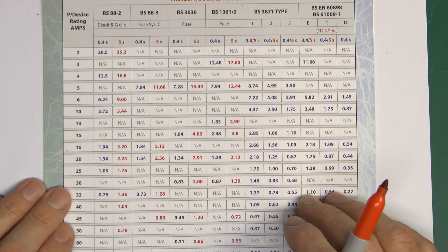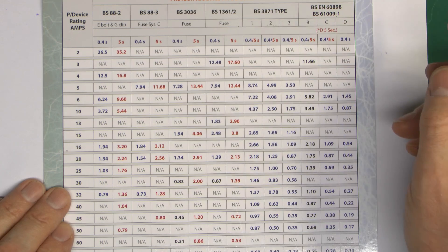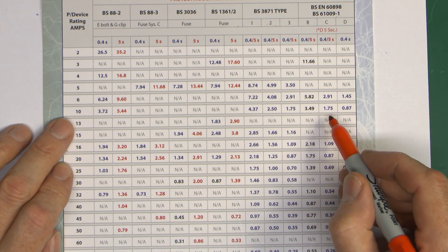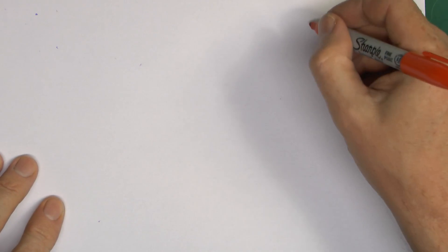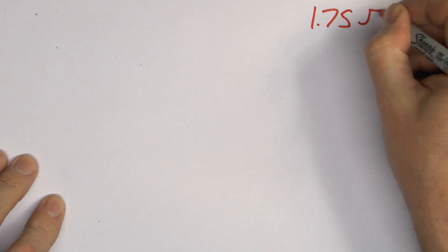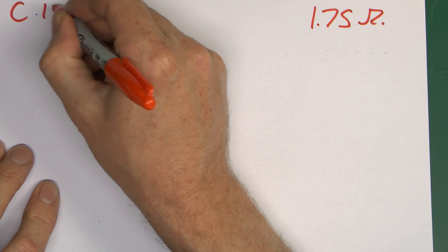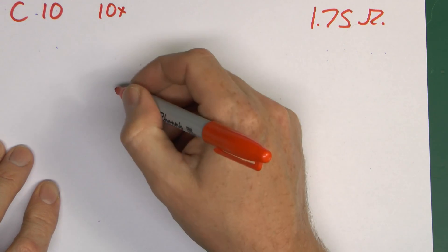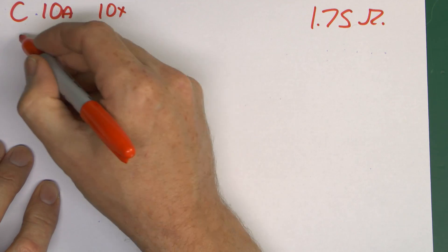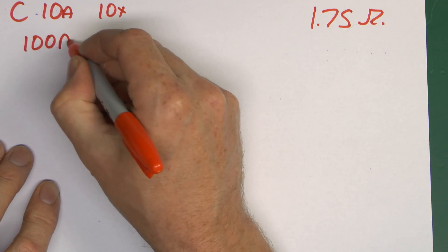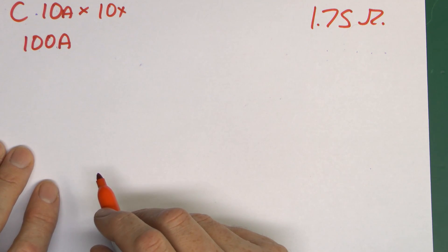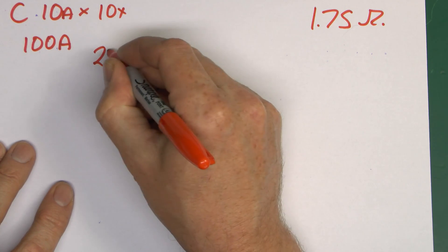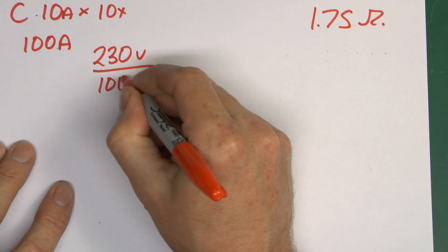Now I'll just do another one of these calculations quickly here, just to demonstrate that. This time, let's say it was a Type C, and this time it was a 10A circuit breaker. So Type C, 10A, so it should be a value of 1.75. So 1.75 is what it's supposed to be. So a Type C, and it was a 10A. Now Type C is tripped between 5 and 10 times, so we're going to assume it's going to be the 10 times, and the current there was 10A. So the current we're going to need is going to be 100A, which is basically 10 times 10.